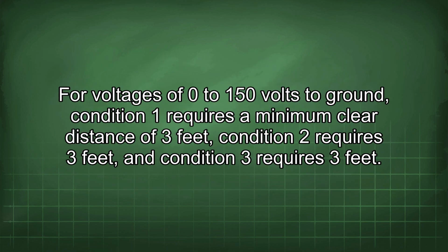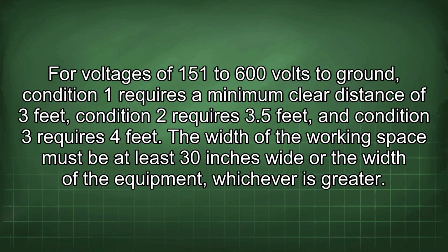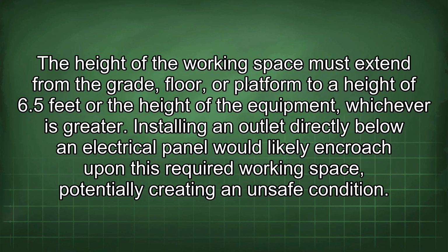For voltages of 0 to 150 volts to ground, Condition 1 requires a minimum clear distance of 3 feet, Condition 2 requires 3 feet, and Condition 3 requires 3 feet. For voltages of 151 to 600 volts to ground, Condition 1 requires a minimum clear distance of 3 feet, Condition 2 requires 3.5 feet, and Condition 3 requires 4 feet. The width of the working space must be at least 30 inches wide or the width of the equipment, whichever is greater. The height of the working space must extend from the grade, floor, or platform to a height of 6.5 feet or the height of the equipment, whichever is greater.